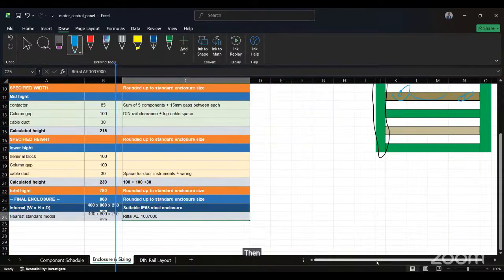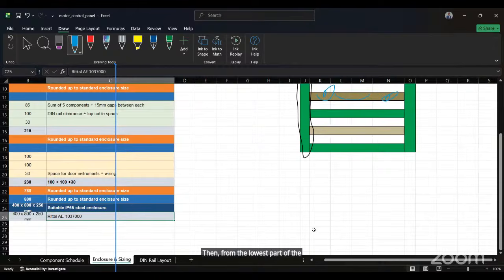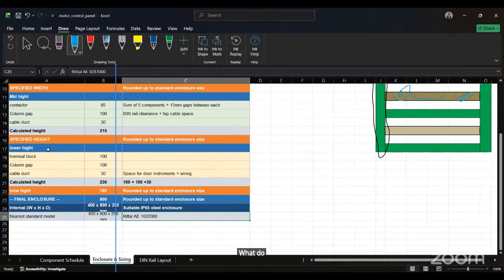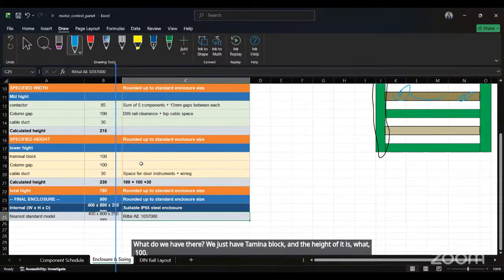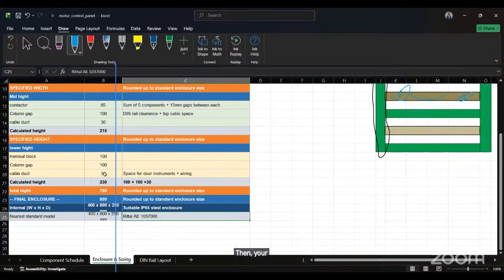Then from the lowest part of the drawing, which is this part, what do we have there? We just have terminal block, and the height of it is 100. Then we leave a column gap of 100, which is the minimum acceptable. Then your cable duct is 30.